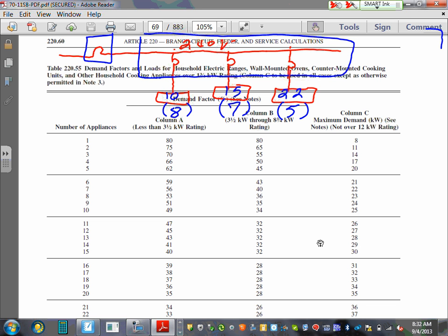Can you guys see that? Remember, these are kWs, so don't forget that each one of these is kW, kW, kW. So I have 10 kW, 15 kW, and 22 kW ranges. 8 of the first one, 7 of the second one, and 5 of the third one. So how many branch circuit breakers will I have? 16 plus 4 is 20. All right. 20 double pole circuit breakers in this panel, plus a main. The main is going to be sitting either inside the panel or outside the panel.